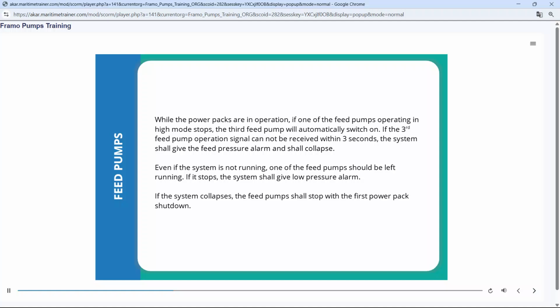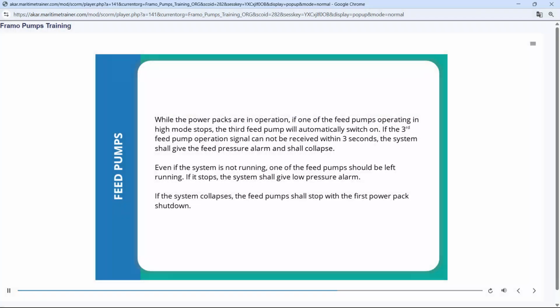If the third feed pump operation signal cannot be received within 3 seconds, the system shall give the feed pressure alarm and shall collapse. Even if the system is not running, one of the feed pumps should be left running. If it stops, the system shall give a low pressure alarm. If the system collapses, the feed pumps shall stop with the first power pack shut down.